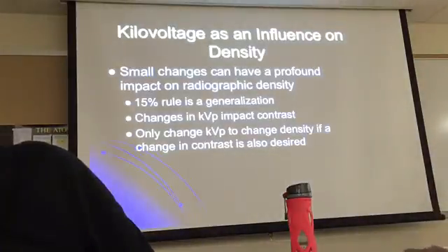A small change in KVP with digital systems can have a profound effect on the image, more than changing mAs. This is just the way the system is. And why do they do it that way? They want it that way so you can still minimize patient exposure. Okay? Make sense? So now we can go back to this part.